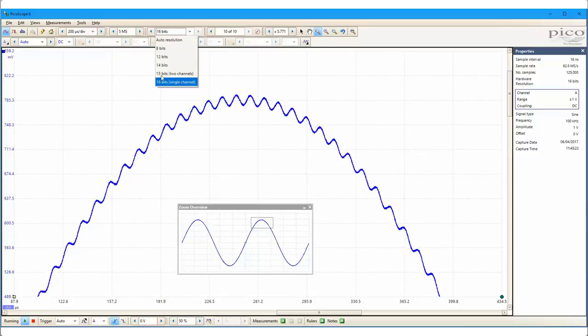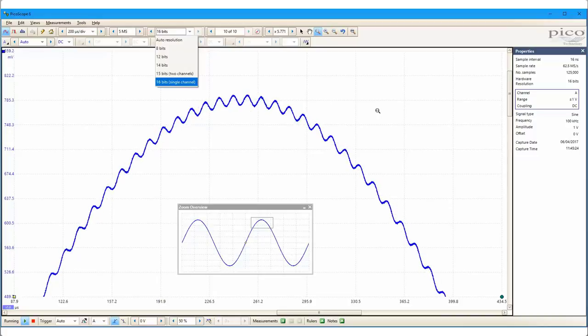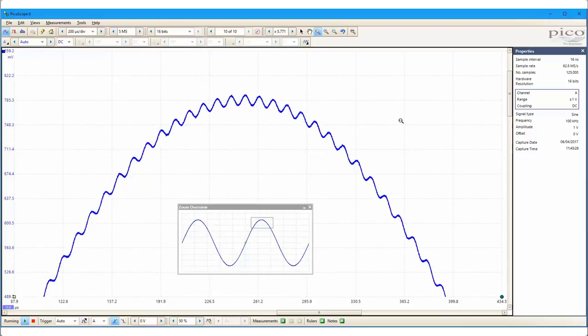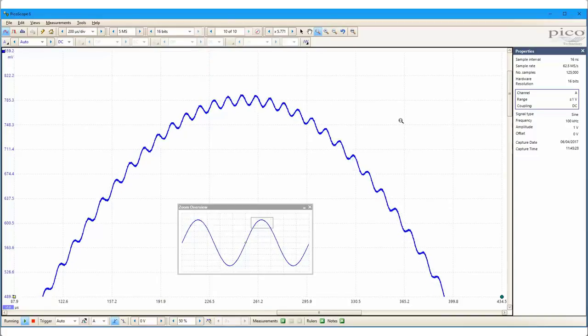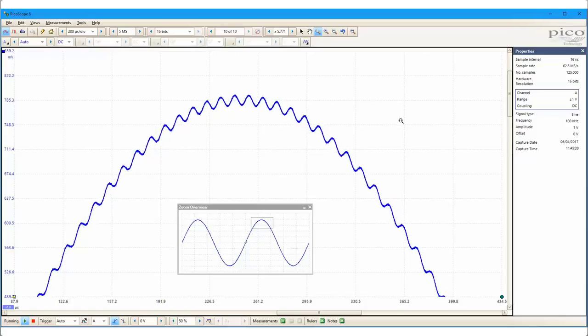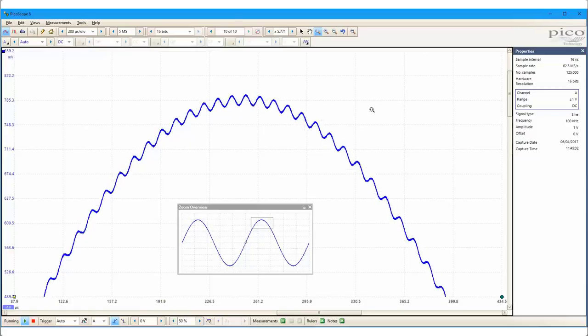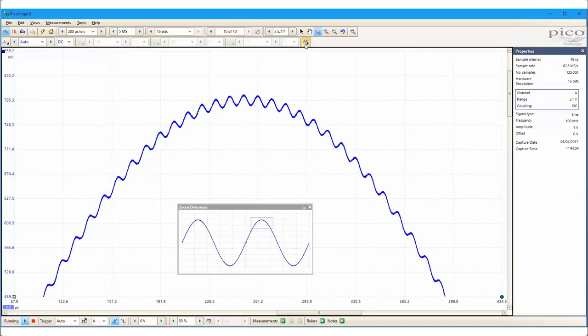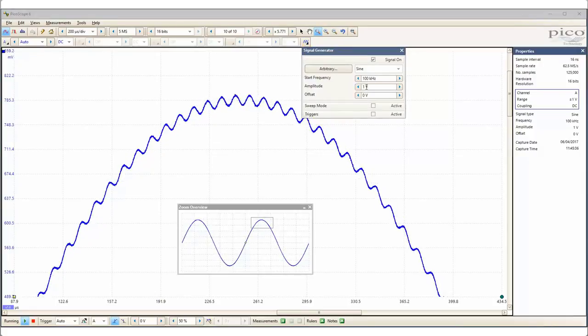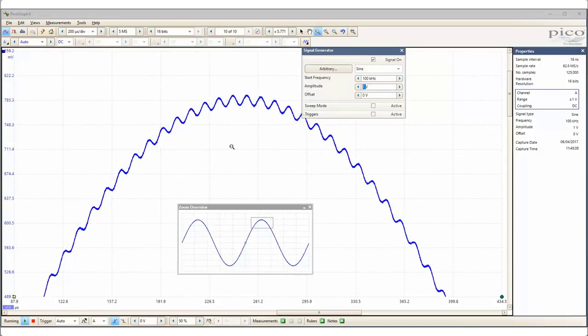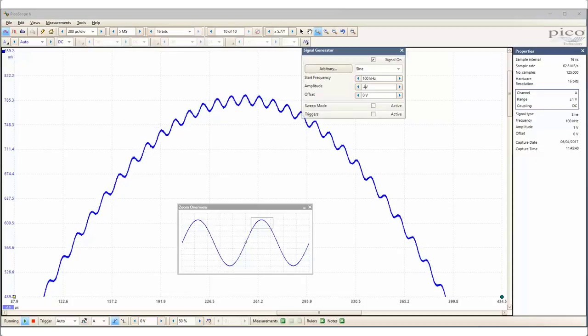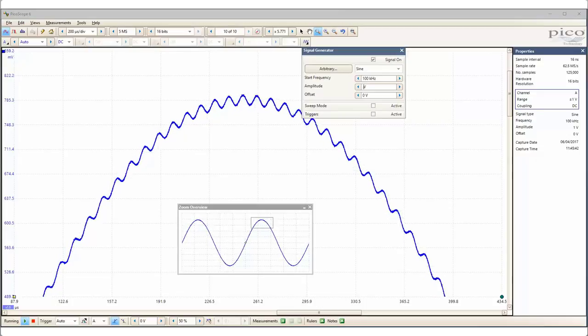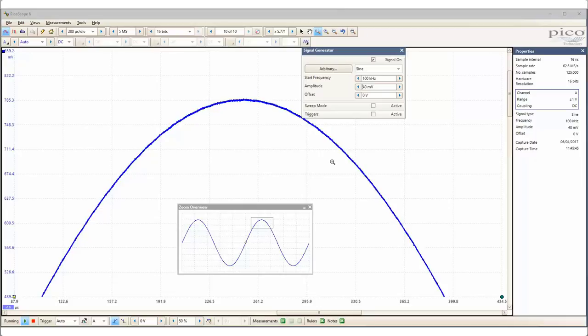Now, we say that increasing the vertical resolution brings a corresponding improvement in the dynamic range of the oscilloscope. So what does this mean, and how can I show this? Dynamic range is the ability to see low-level signals in the presence of high-level signals, and is often measured in dB. To show this, I'll reduce the interference signal until it's no longer visible in the time domain, even in 16-bit mode.